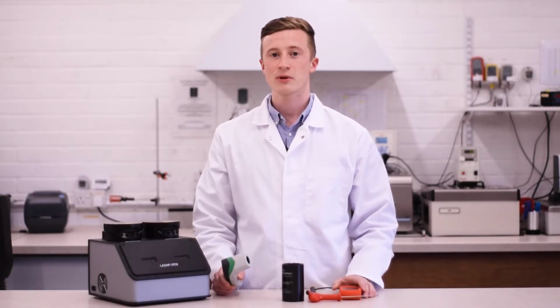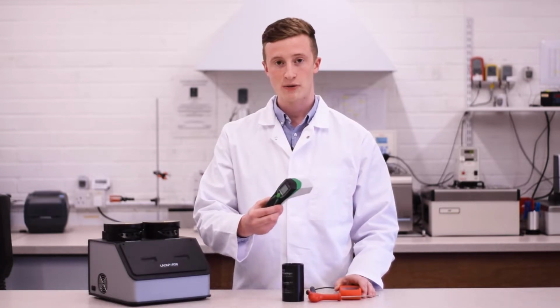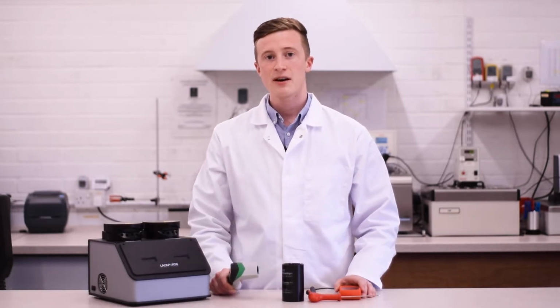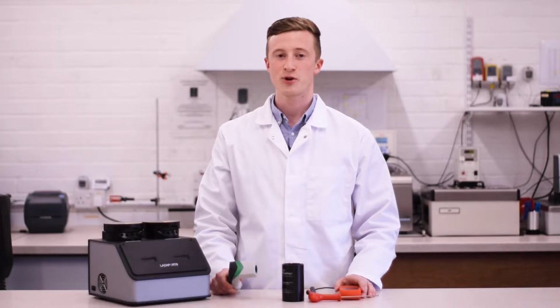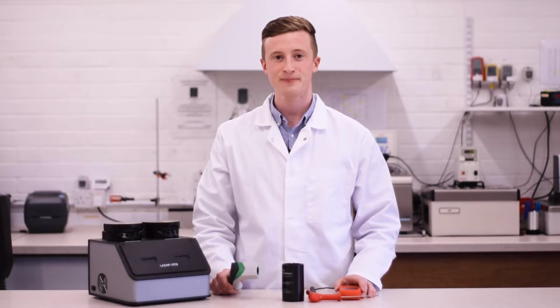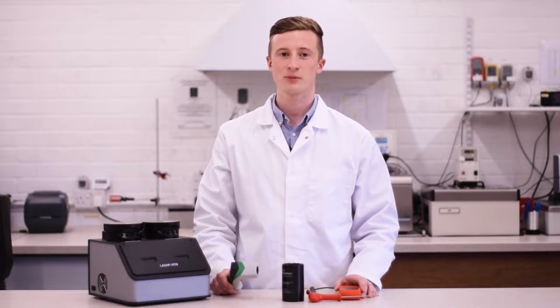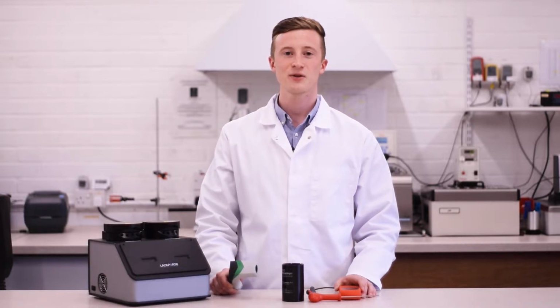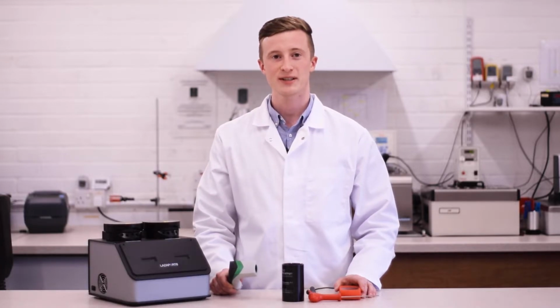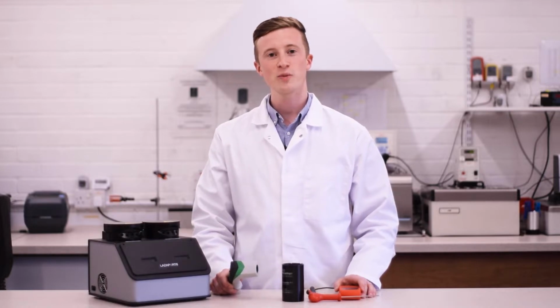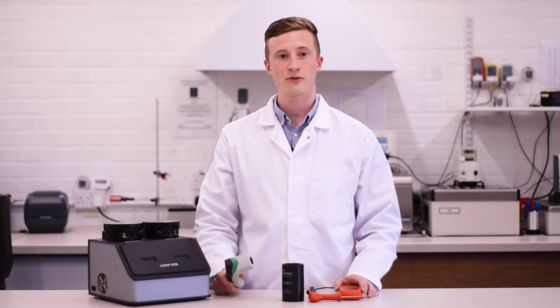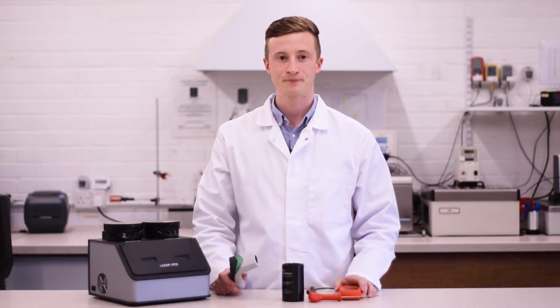Typically, infrared thermometers, such as the LaserScan 205, which I have here, have a wider accuracy tolerance than probe thermometers. This makes it all the more important to check them more regularly. For details on how to get the most reliable and repeatable infrared thermometer readings, see our separate video on infrared thermometer best practice. So there are two main ways to verify how your infrared thermometers are reading.